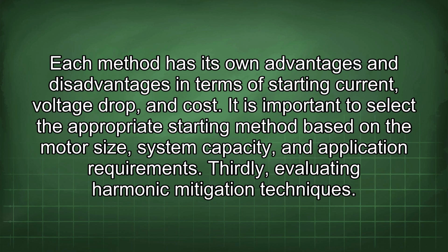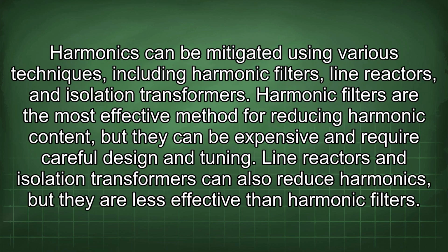Thirdly, evaluating harmonic mitigation techniques. Harmonics can be mitigated using various techniques, including harmonic filters, line reactors, and isolation transformers. Harmonic filters are the most effective method for reducing harmonic content, but they can be expensive and require careful design and tuning. Line reactors and isolation transformers can also reduce harmonics, but they are less effective than harmonic filters.